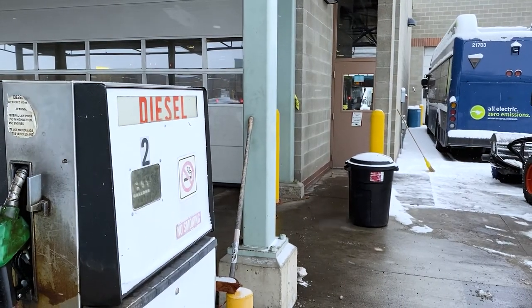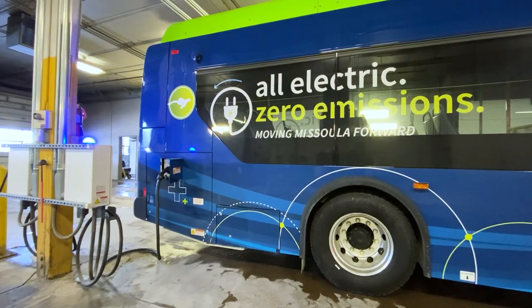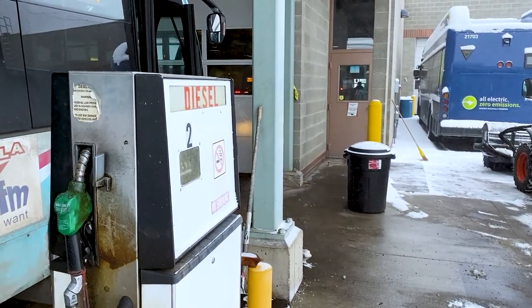Is operating an electric bus more affordable than operating a diesel bus? That is a complicated question because we have to look at a couple of different things: short-term things like variable fuel costs, and long-term things like overall community health and air quality. When looking at the short term, it can actually be comparable or more to operate an electric bus over a diesel bus. When we plug one of our electric buses in, we pull a lot of power from the grid, and the largest cost associated with charging our buses is actually a demand rate charge — a charge that is applied every time we demand a lot of energy from the grid. Outside of the demand rate charge, it can actually be more affordable mile to mile to charge an electric bus than fuel a diesel bus. Looking at the long term, we sincerely believe that our commitment and transition to a zero tailpipe emissions fleet benefits all of us now and in the future.